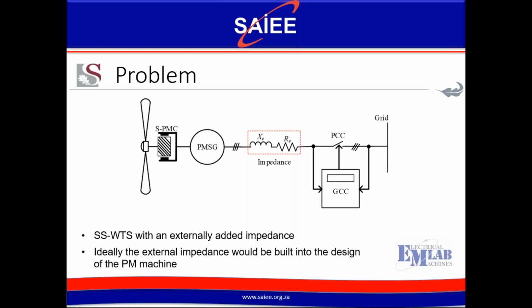Okay, so the power factor couldn't really be controlled because it is a normal permanent magnet synchronous generator without any field windings. So its power factor is completely dependent on what's happening with the grid. All that we did was look at what would happen to this particular machine's performance when we manually vary the grid voltage, or we manually vary the input power supplied to the generator. Ideally its optimum power factor would obviously be 1, but it was designed to be able to operate at around 92% efficiency for a power factor of between 0.92 and 0.95, if that answers the question.